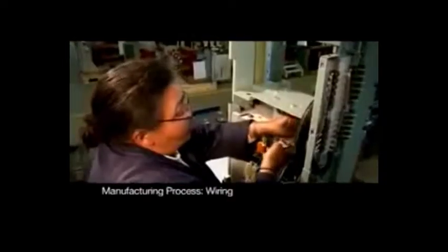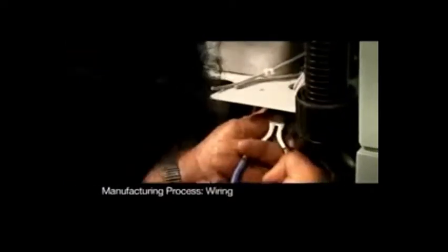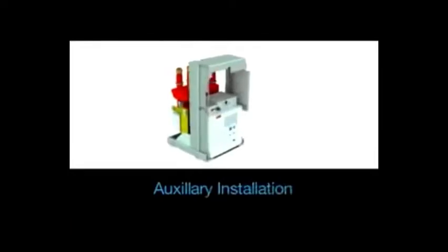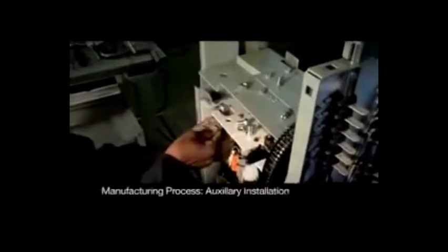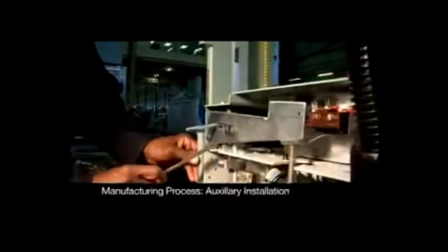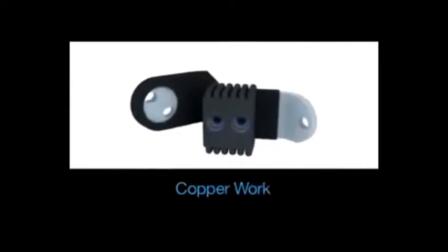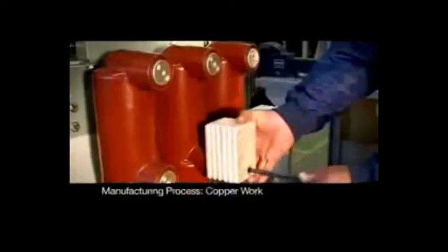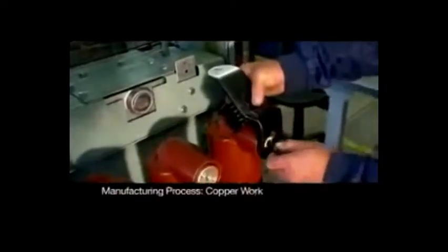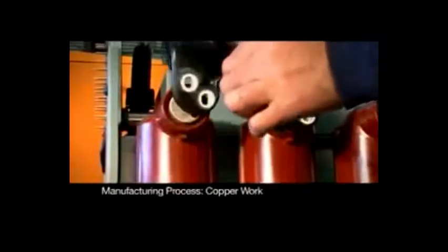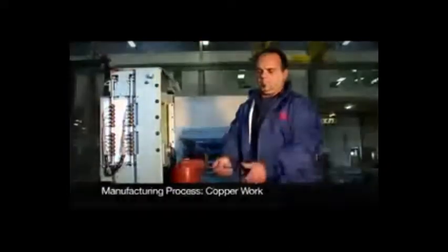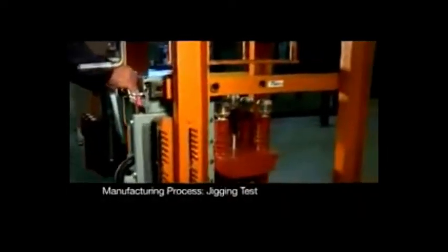Client-approved wiring diagrams are given to the wiring staff to wire the unit according to the client's specifications. The installation of the tripper assembly is a vital process to ensure that the unit will operate safely, trip safely, and function correctly. The copper work is installed with the riser to prepare it for the jigging and final alignment process. At this stage, the breaker will be jigged. These jigs have been bolted specifically according to the Reyrolle panels.